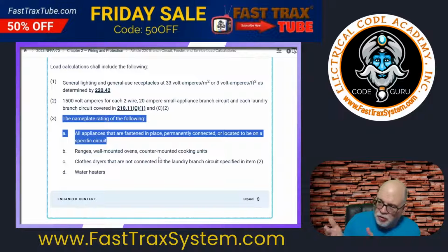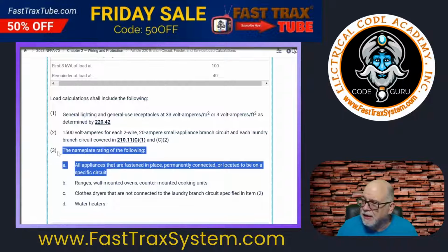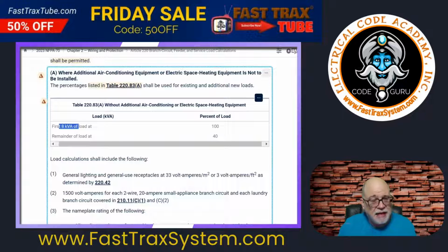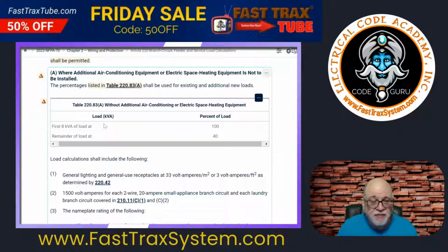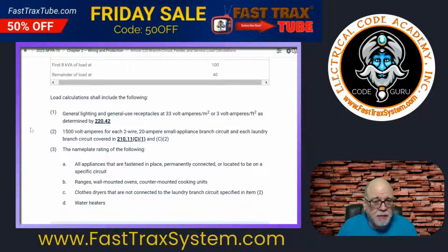Now, since you have to gather all of the information anyway, then you might find that you're better off doing the optional method anyway. Okay, and that means the first 10,000 is at 100%, and then the remainder at 40%. But this method might be a little smaller because only the first 8,000 is at 100%. So if it's existing, you're permitted to do this. You could go back and use the optional method or even the standard method, but you're permitted to do this. This might yield something that's going to work out better for you.